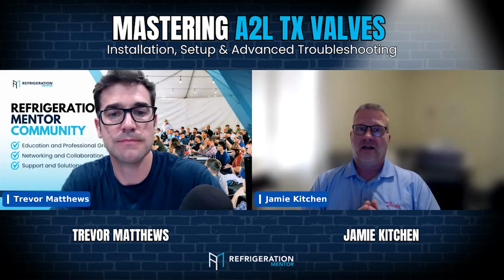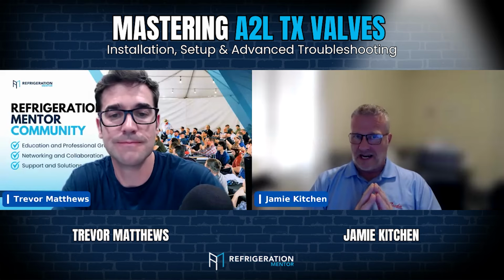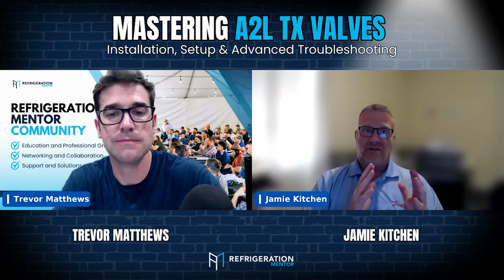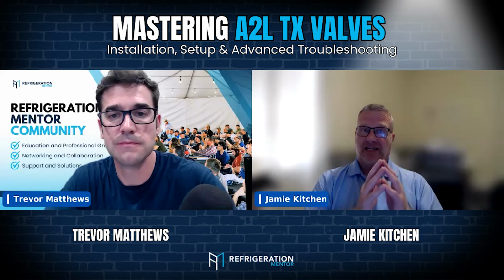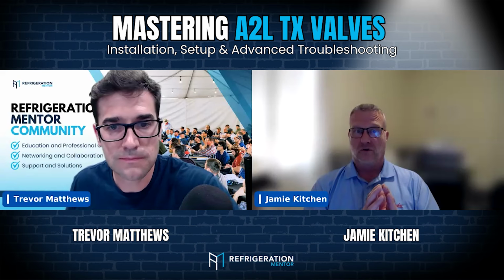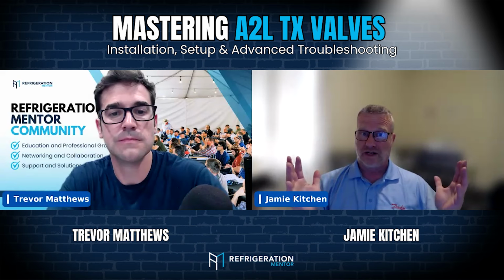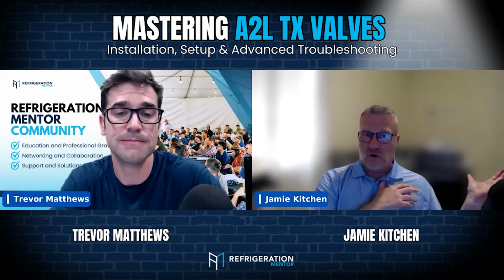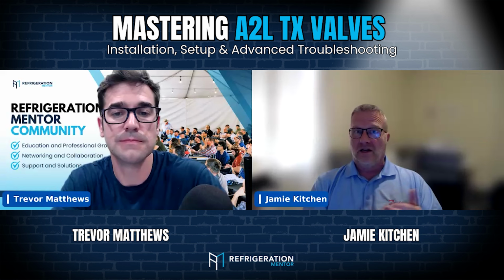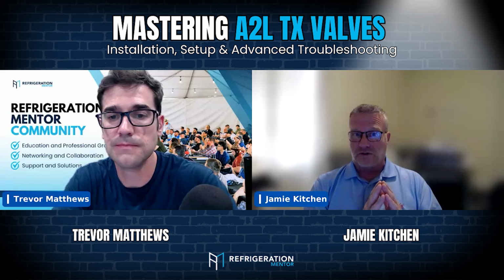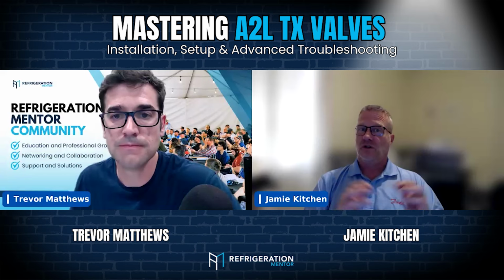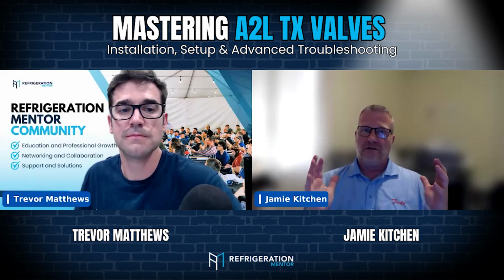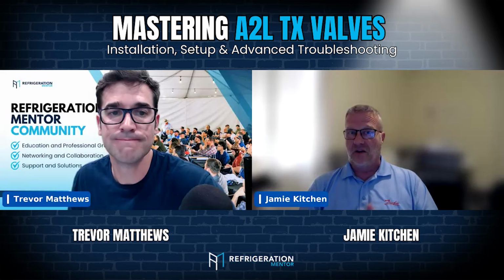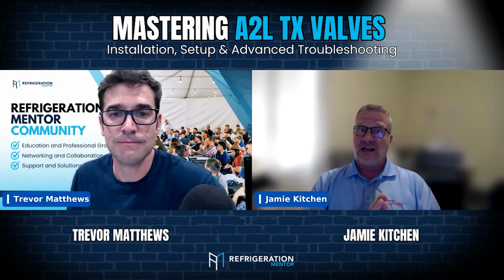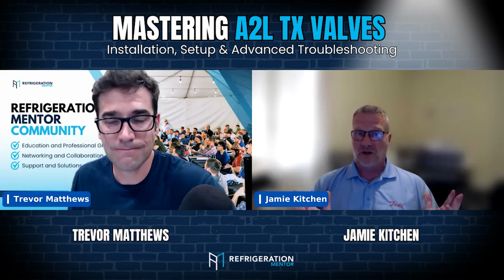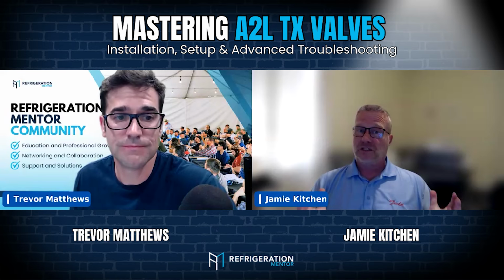We call that glide. From a calculation standpoint, working with a refrigerant blend that acts like a single compound is much easier for a lot of people because we're used to that. We're used to 22. We're used to, say, 404A or 410A. You don't have to really worry about it. That was one of the things that challenged people with 407C, where all of a sudden you had this refrigerant with glide. It threw an extra set of calculations in there that, if you got them wrong, substantially impacted the performance of the system. People were cognizant of that. But that's what these blends mean.